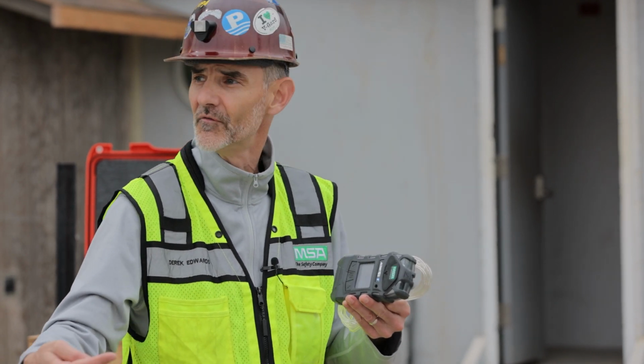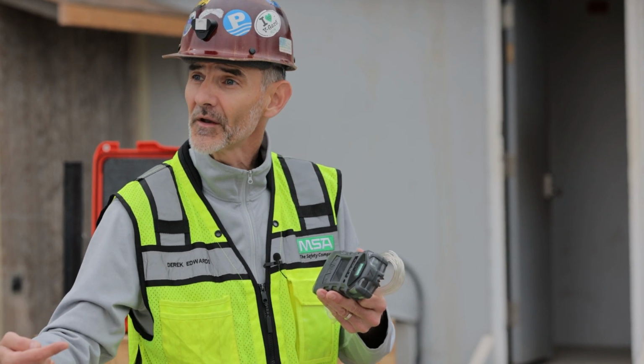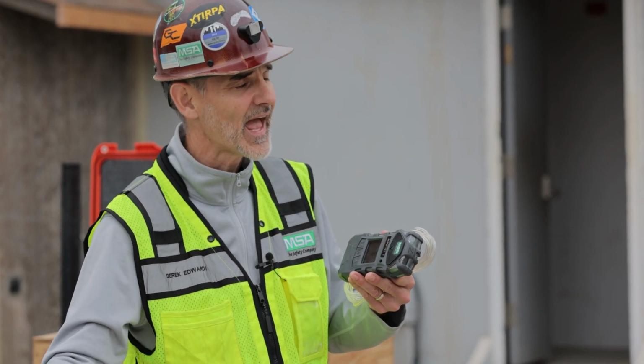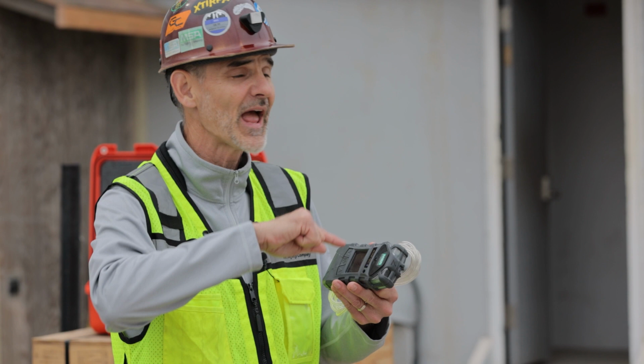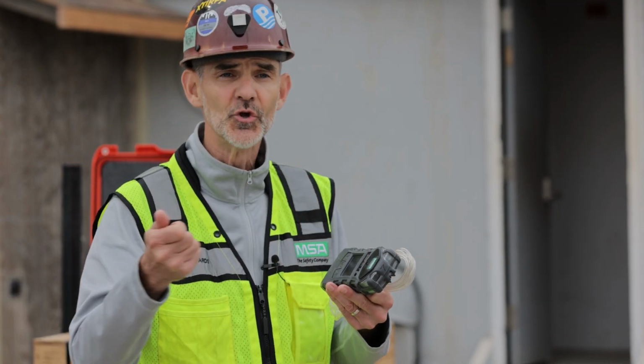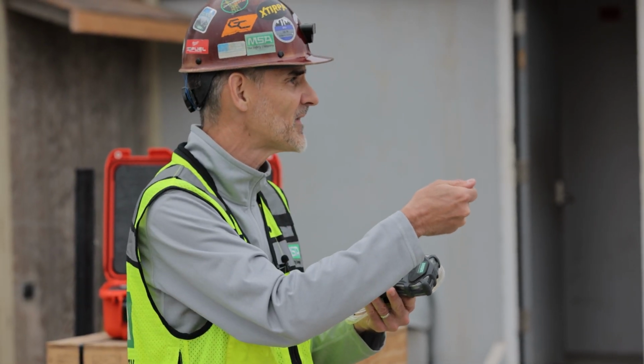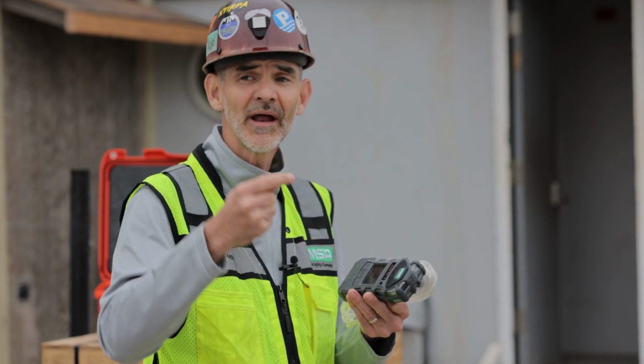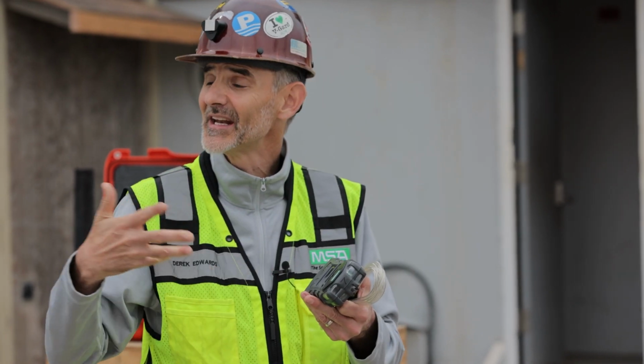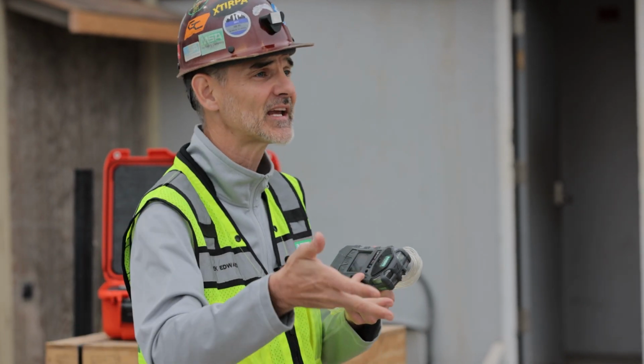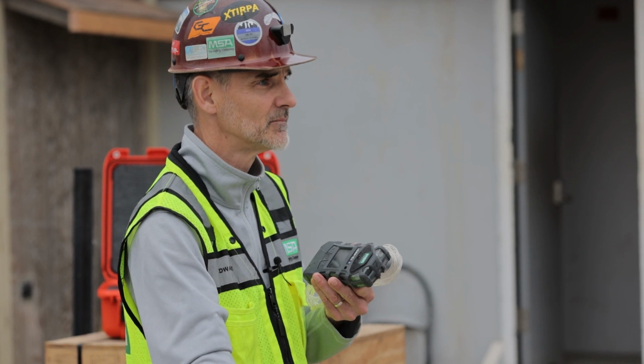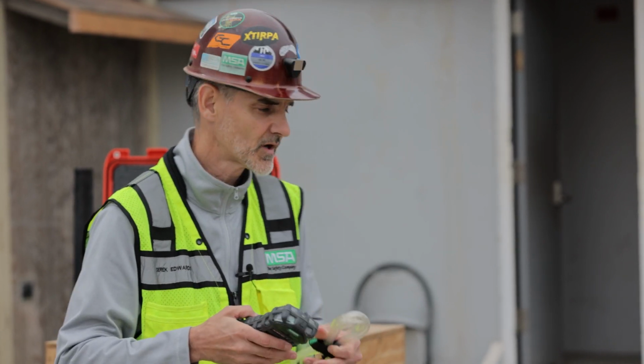Little preview for you. The important thing here is that we block the end of that, because if we have a leak in that system, you're not pulling a sample from the end of that probe. You might have a leak, which means you're getting diffusion and you're not checking the bottom of that space because we have a leak in that system, okay?